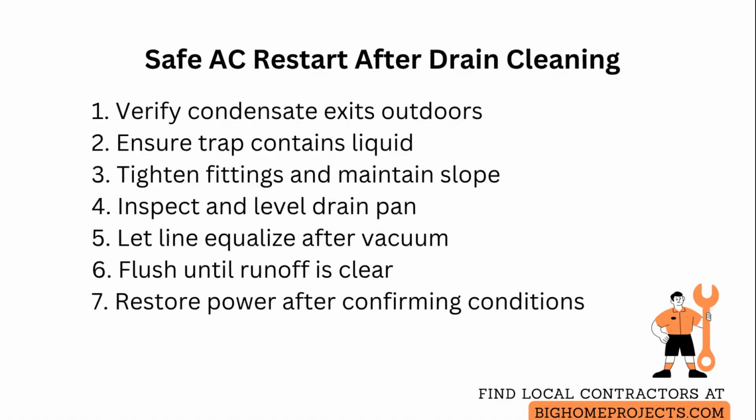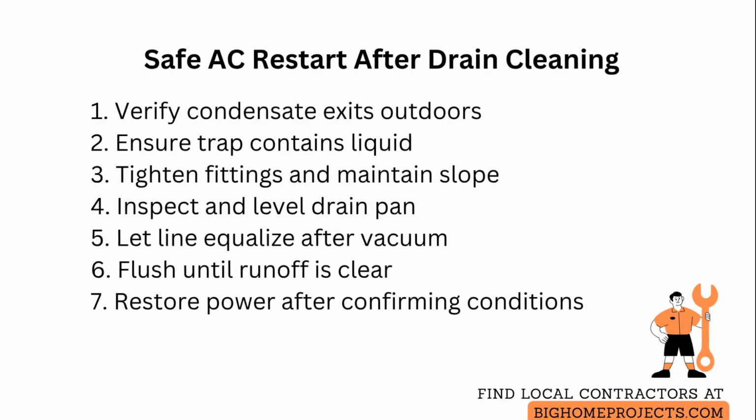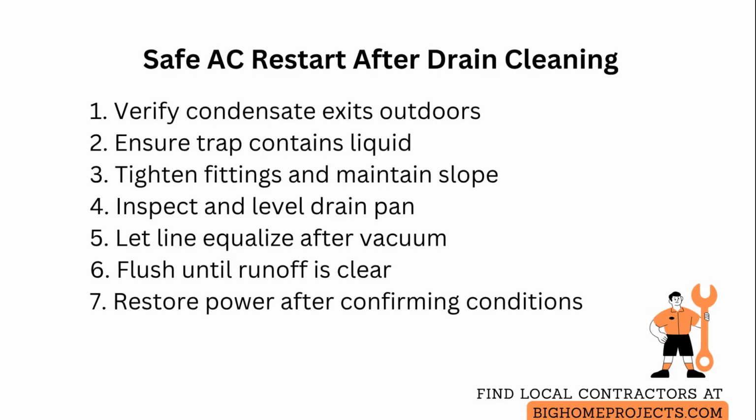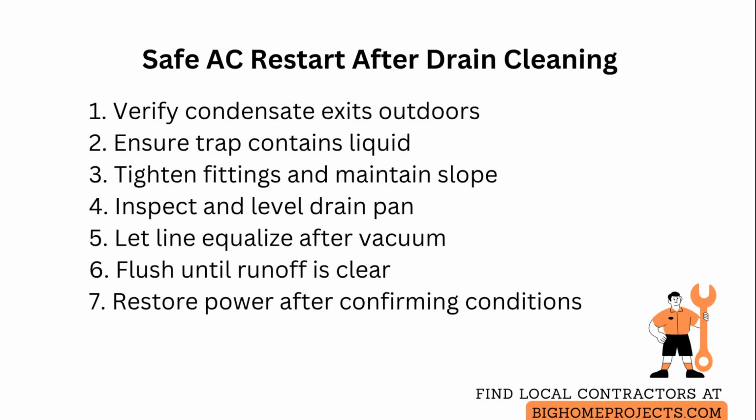Check every fitting along the drain run for tightness and correct slope so water moves by gravity at about 1/4 inch per foot where possible, and will not pond in low spots. Inspect the drain pan for cracks and confirm the pan is level or pitched to the drain outlet.